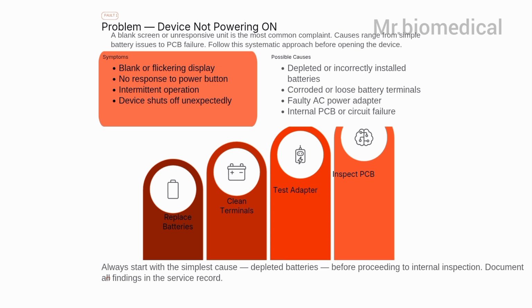So the first problem which we are seeing here is device not powering on. Suppose a nurse calls you and says, "Sir, the BP apparatus is not switching on," what will you do first? What many beginners will think is to immediately open the device, but a good service engineer always starts with simple checks. I have mentioned this in every troubleshooting video, so don't get bored of it because it is very important. First, check the battery. Are the batteries discharged? Are they inserted correctly? Next, inspect the battery terminals. Do you see any corrosion or rust? If yes, clean it carefully. If the device uses an adapter, check the adapter voltage using a multimeter.